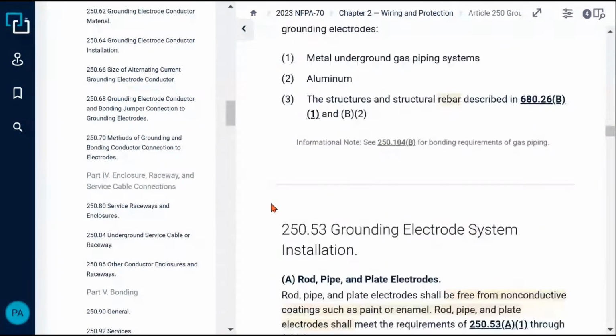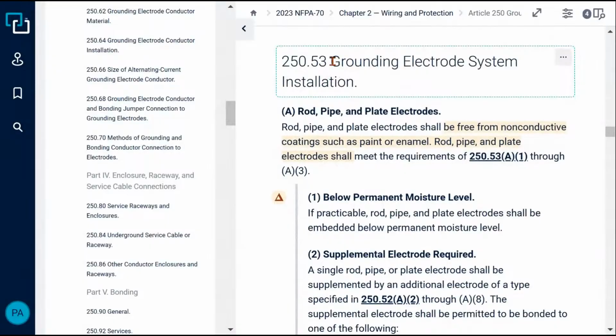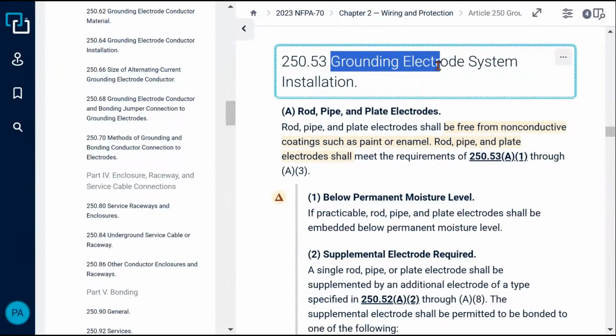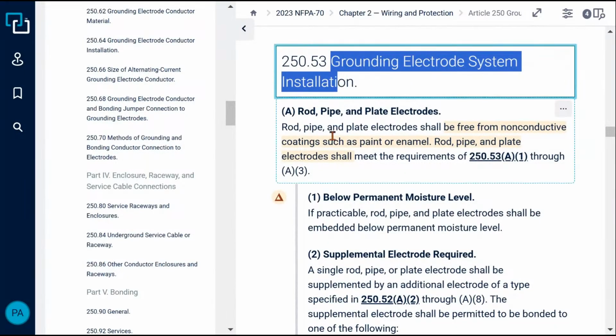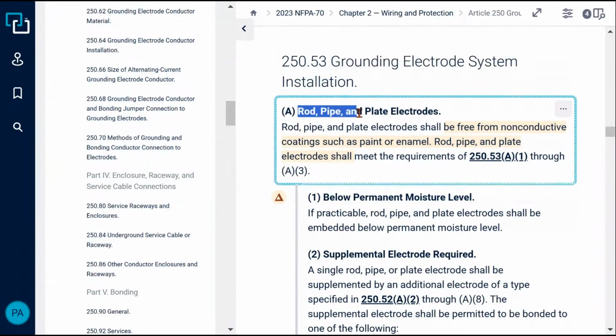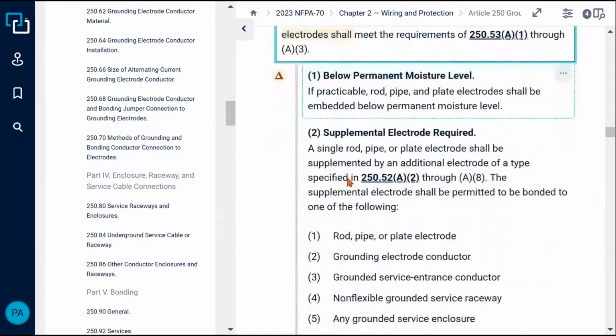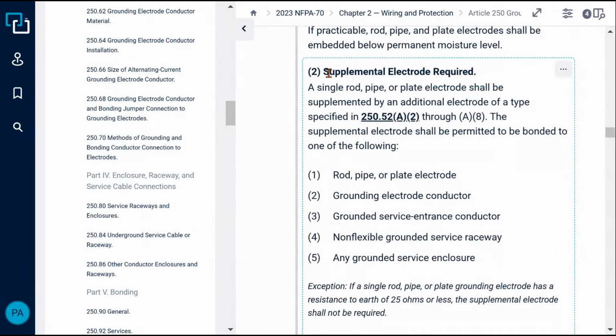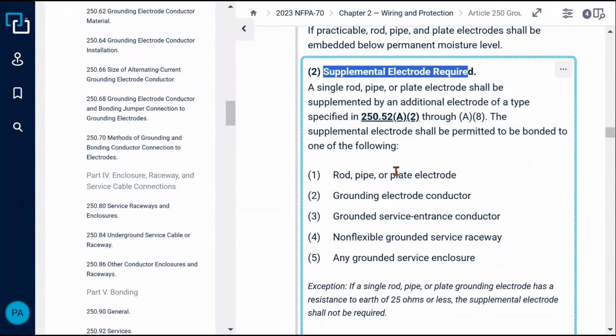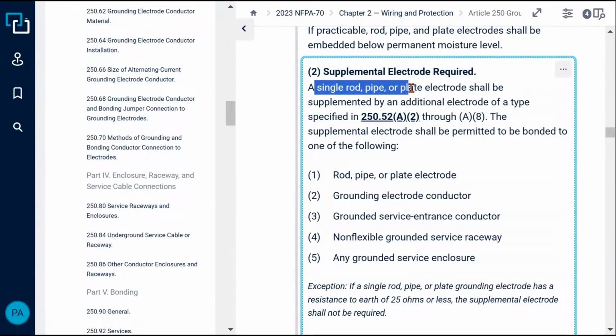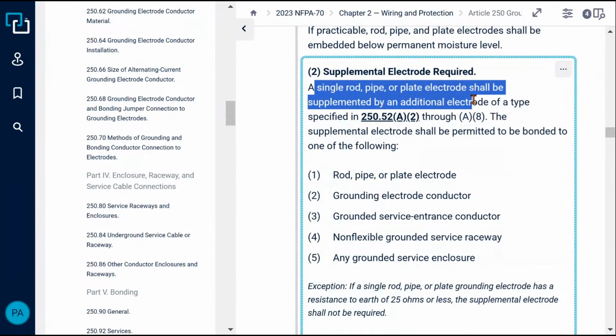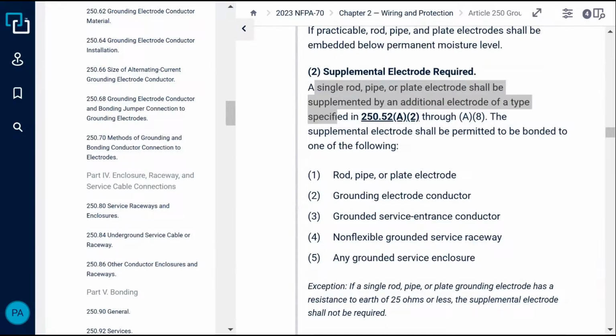So what I was talking about is this one right here, the grounding electrode system installation for rod, pipe, and plates. See this right here? This is where it talks about the supplemental electrode required. It says a single rod, pipe, or plate electrode shall be supplemented by an additional electrode of the type specified in 250-52 A2 through A8.